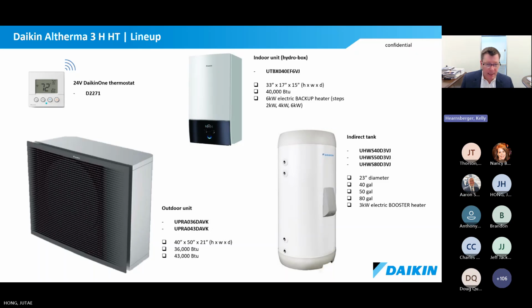And then, of course, the tank size depends on your loading of water usage, and that's always done, of course, in a particular calculation or method based on how many people, what is the water usage pattern. But this has a very strong recovery rate for water heating. And even if you were in heating or cooling mode for the space temp and you needed to come back over to domestic hot water, you could have a completely empty tank and fill that 50-gallon tank up in around 55 minutes. So with 130, 140 degree water, it's a very strong recovery unit.